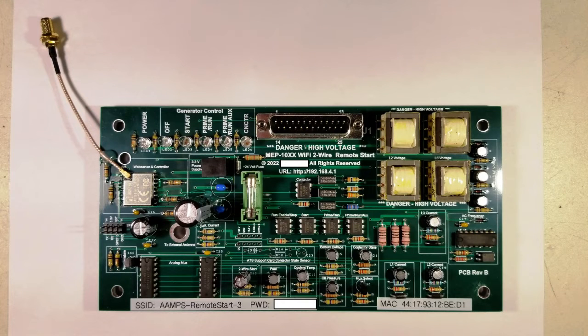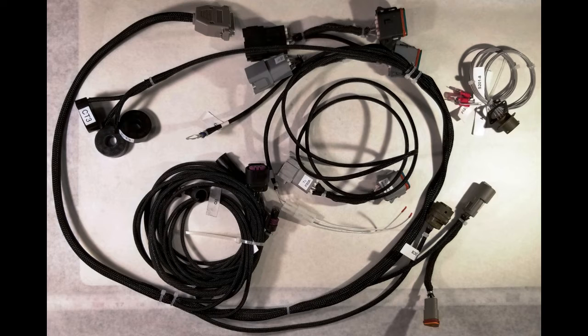The control card assembly is 4 by 8 inches. In the upper left is the antenna lead for the external Wi-Fi antenna. Next to it are a series of LEDs to indicate the status of the card. In the top center is the connector for the provided cable harness to connect to. Provided with the system are 2 cable harnesses. The large one on the left is used to interface to all the sensors on both the engine and generator. The small harness on the right gets installed in the DCS housing to provide access to the master start switch.